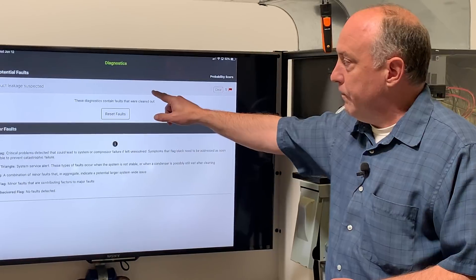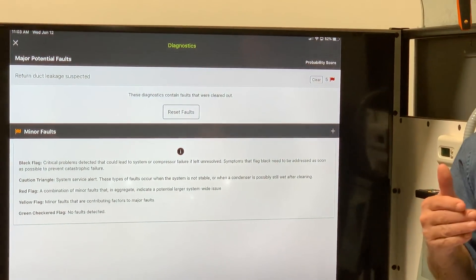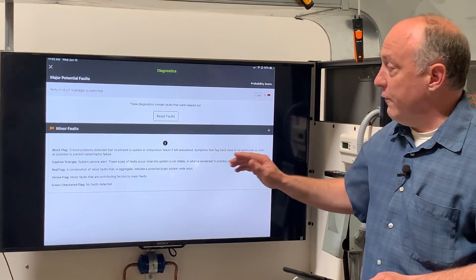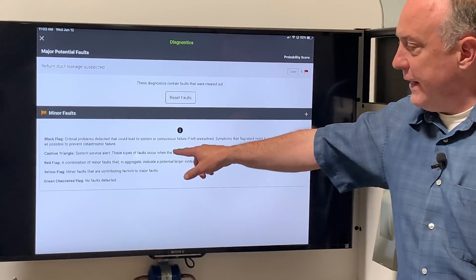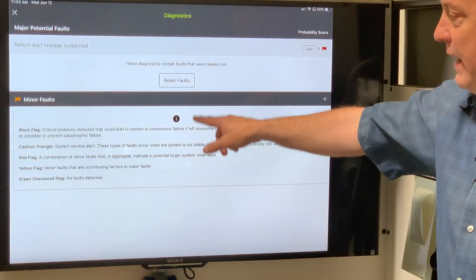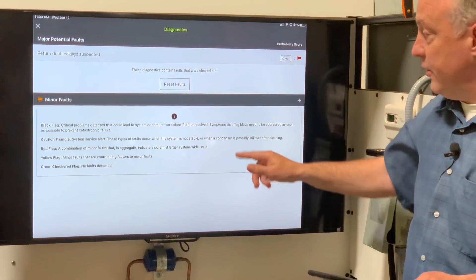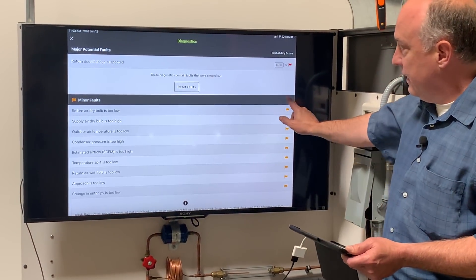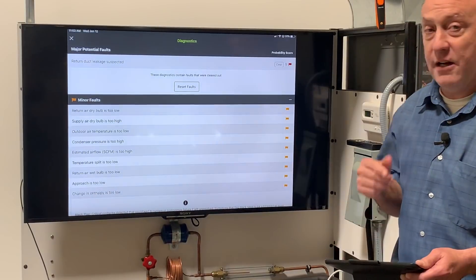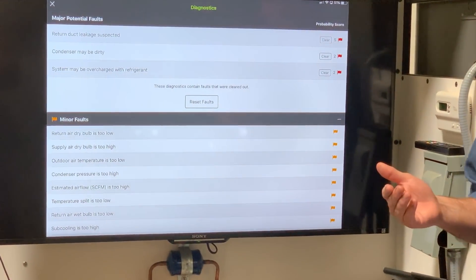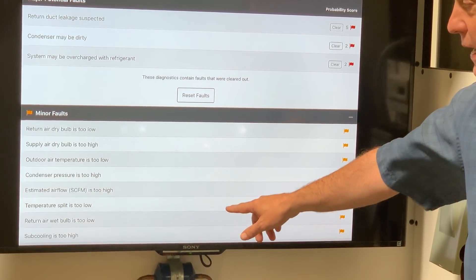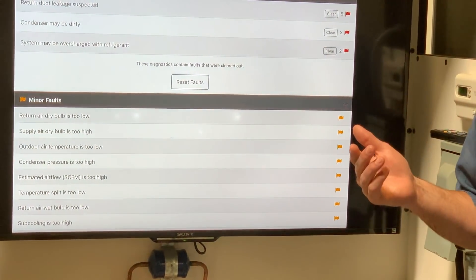When I tap on that red flag, it's going to tell me a major potential fault. In this case, we have return air duct leakage suspected — this is a new fault we just added. It's an aggregation of a whole bunch of minor faults. At the bottom, it tells you what a black flag, a caution triangle, and a red flag each mean. A red flag here indicates five different faults giving us that indication of return duct leakage. If I tap on the plus sign, these are all the minor faults aggregating to tell us that major fault is present: condenser pressure too high, estimated airflow too high, and the split's too low — all indications of return duct leakage.